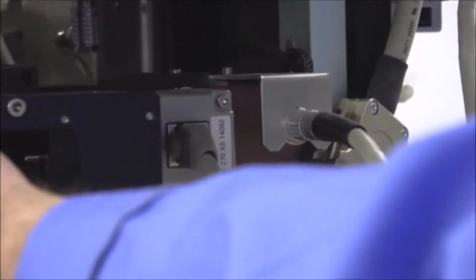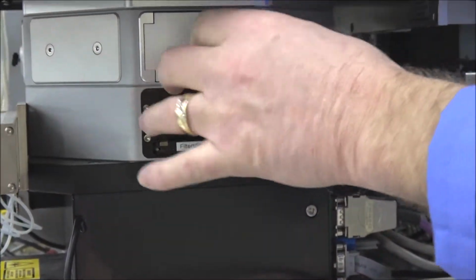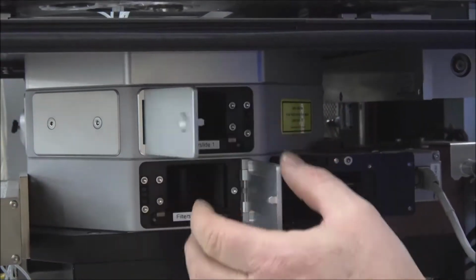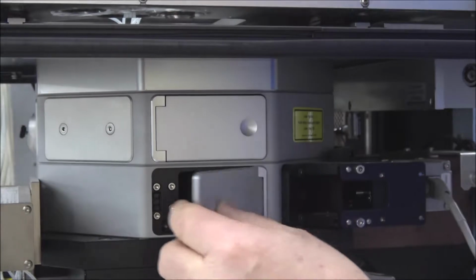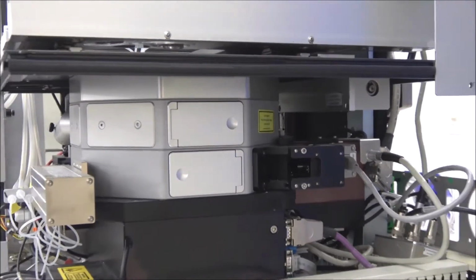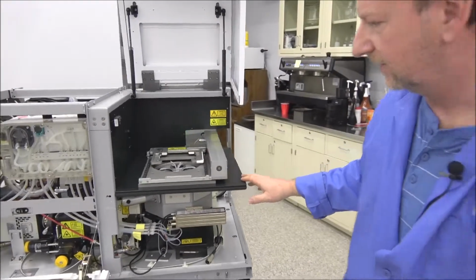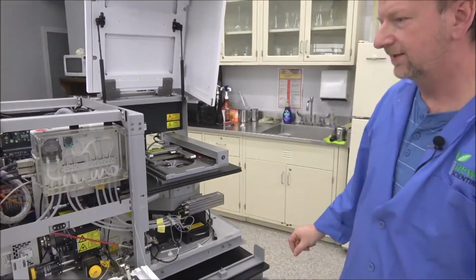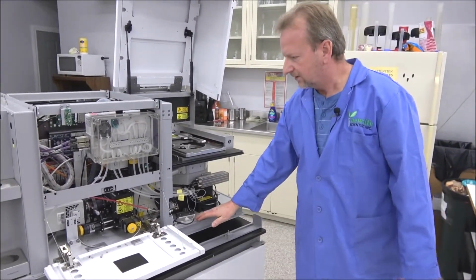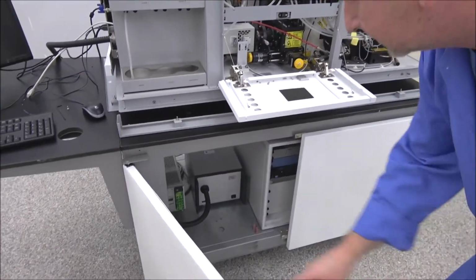And while we're here, I'm just going to open up the slide filters for the UV. So you have 2 of them. You have the excitation, and I forget what the other one is. But these are all controlled through the software, which I'll show you on the next video. So a lot to these machines, but like I said, they're very easy to access everything. I have multiple machines like this for parts. If you do run into a problem, we perhaps can help you out on that. So our UV light source is hooked up. The UV light source is on down there.